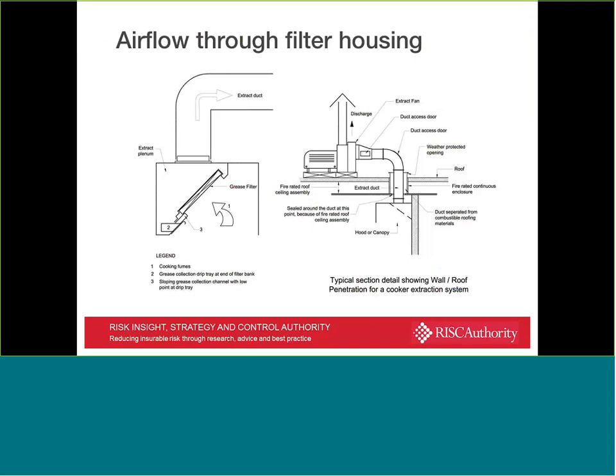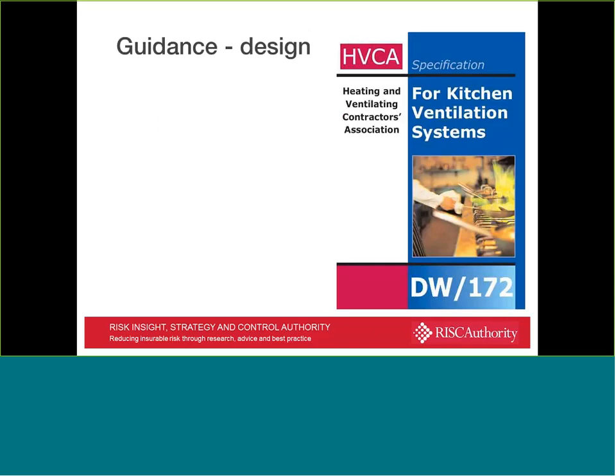On the right hand side, you can see a typical detail of a wall and a roof with penetrations for a kitchen extract system. Again, it simply shows the hood or canopy with the extract ductwork passing through the roof, the need for a fire rated continuous enclosure to prevent a very hot duct or a fire in a duct, should it occur, conducting heat to surrounding materials and spreading the fire further, and other important aspects such as the fan, which is set outside of the ductwork itself, in order to draw the air through, albeit that it will still become contaminated very often. The access doors that are there for cleaning, and the discharge point itself.